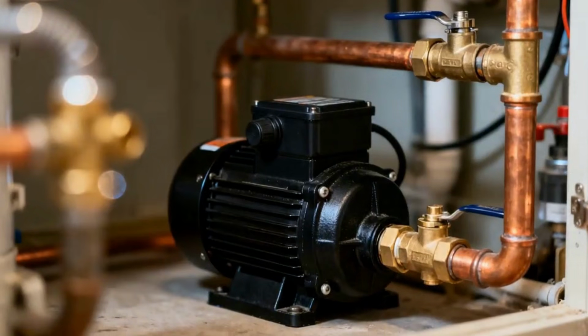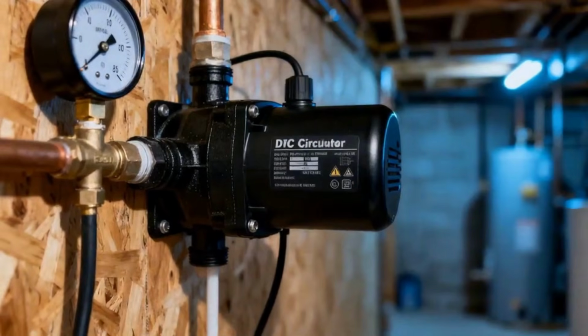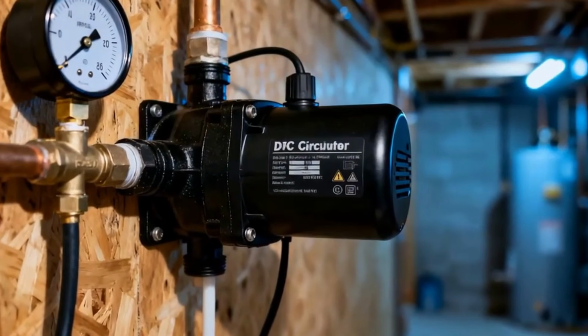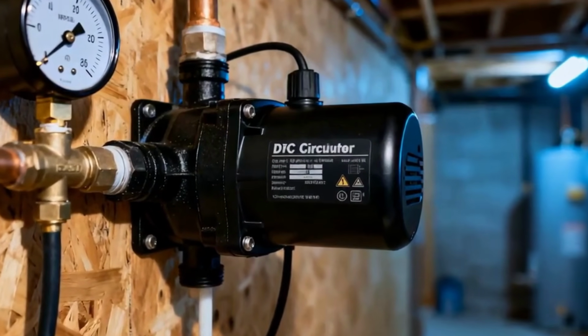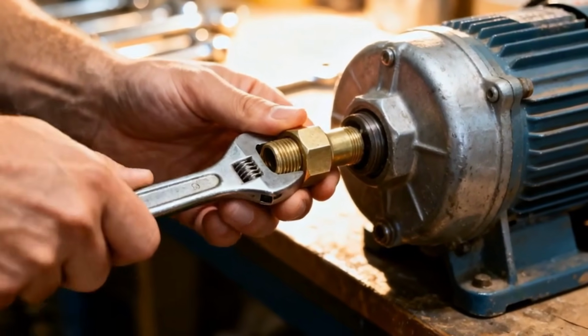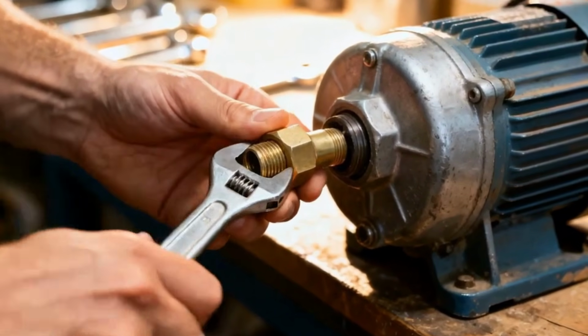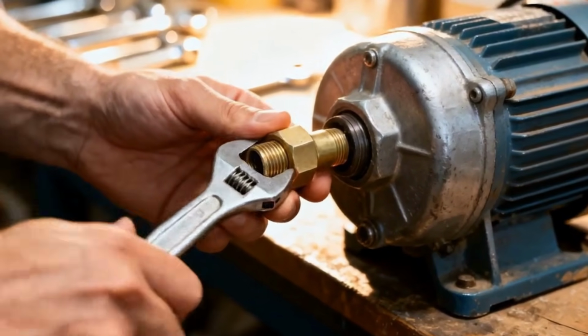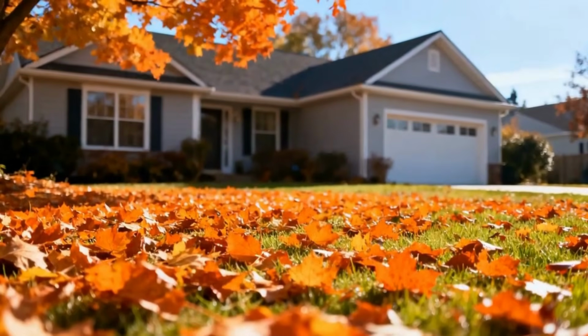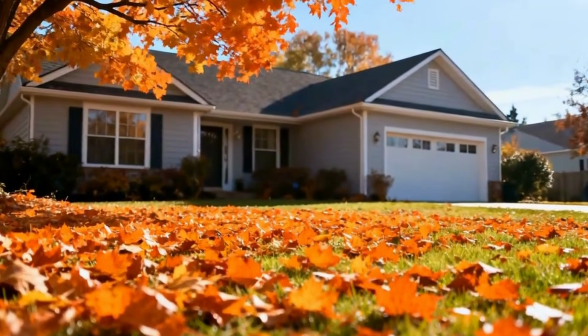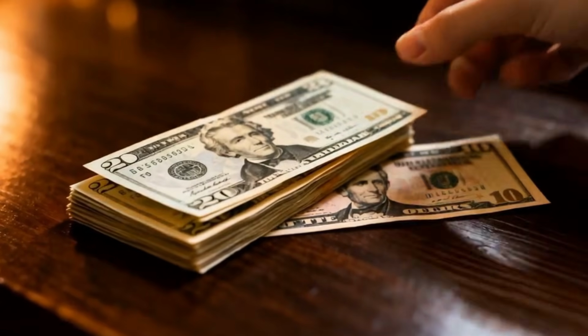The pump is the only part that will eventually fail. The brushless DC circulator pump has a typical service life of 15 to 20 years. When it fails, you unscrew it from the brass fittings, replace it with another $36 pump, and you're back online in 20 minutes. Over a 60-year horizon, you'll replace the pump 3 or 4 times. Total lifetime maintenance cost about $120.